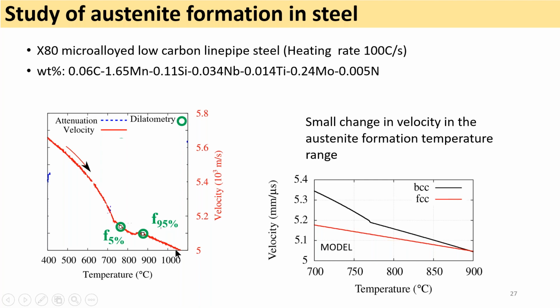What I want to show in this slide is that the austenite formation is not very obvious in a velocity plot, and I illustrate the reason why in this plot. If we look at the speed of sound for BCC ferrite in black and the speed of sound for austenite FCC, we see that in the range of temperature where the austenite formation occurs, those two velocities are very similar. It is therefore often considered a challenge to measure the austenite formation using this parameter.